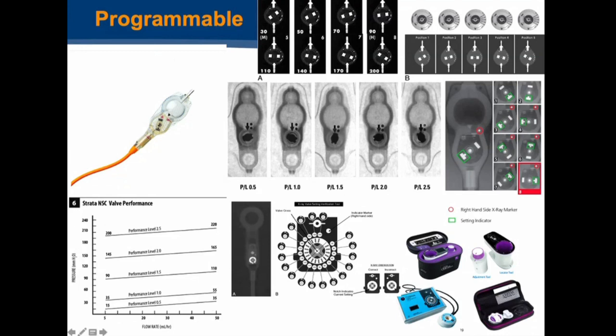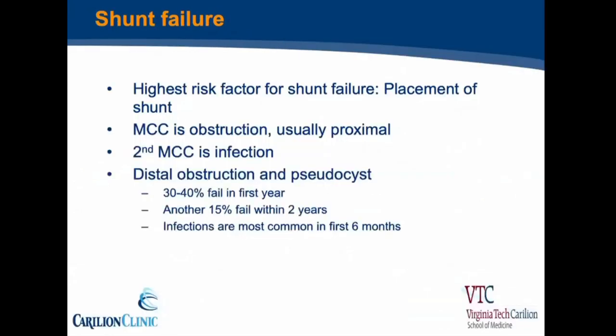So 2.5 is a pretty high setting, as opposed to, if we set it at 0.5, the valve's going to open up somewhere between 1.5 and 3.5, really low pressure. So we do have to be a little careful with how aggressive we're programming these valves. In terms of shunt failure, probably the biggest risk of a shunt failure is the placement of a shunt. So there's a high complication rate, not at Carilion, just throughout the entire country.